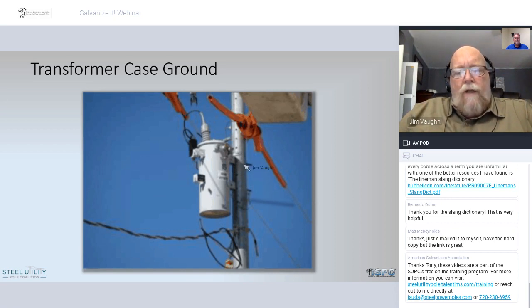I also did a fatality investigation where a lineman climbing a wood pole to troubleshoot a transformer didn't realize that ground connection was gone. And with that ground connection gone, the case of this transformer had 7,200 volts on it. As he climbed the wood pole, when he got up there and reached out to steady himself, he touched the transformer case, and he was killed.